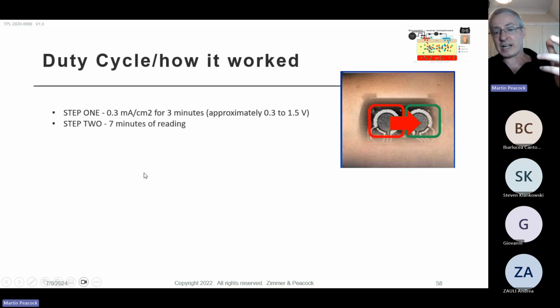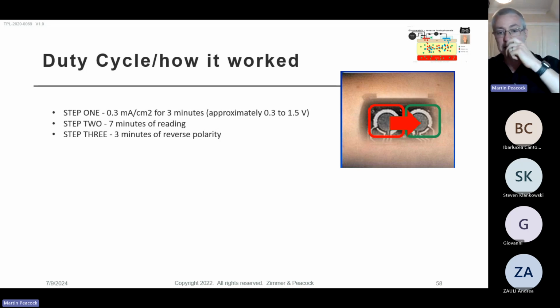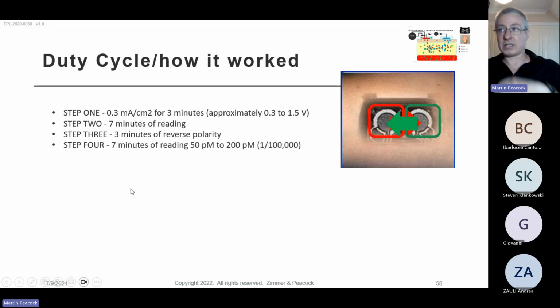It would extract for 3 minutes and then it would read for 7 minutes. So they're doing an extraction and then a reading. And then they would reverse the polarity. So essentially it must have had 2 glucose sensors on it and 2 extraction zones, and they were reversing the polarity and then repeating the cycle where they would do an extraction and a reading.